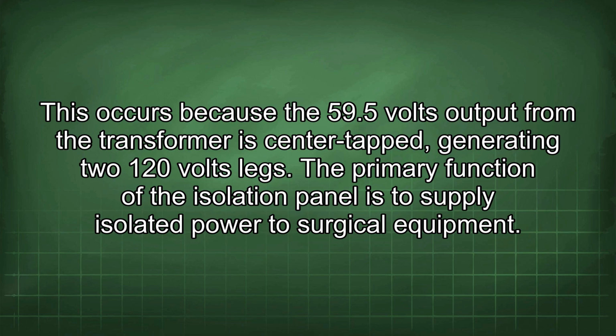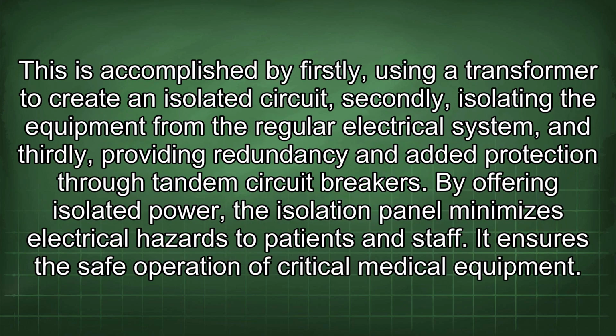The primary function of the isolation panel is to supply isolated power to surgical equipment. This is accomplished by, firstly, using a transformer to create an isolated circuit, secondly, isolating the equipment from the regular electrical system, and thirdly, providing redundancy and added protection through tandem circuit breakers. By offering isolated power, the isolation panel minimizes electrical hazards to patients and staff. It ensures the safe operation of critical medical equipment.